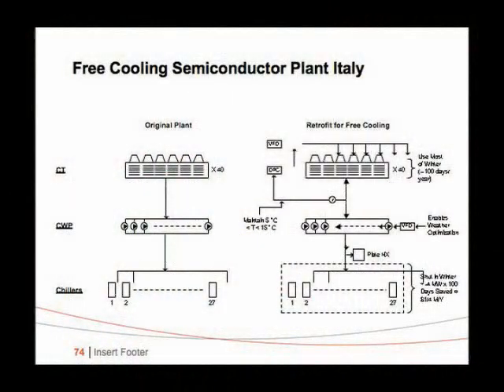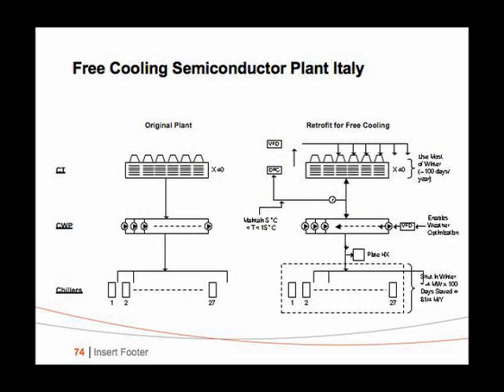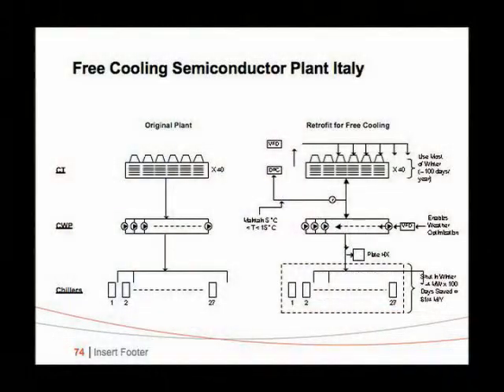But there's also good news. Italy. Some people used to run all the plants in winter. So we say, hey, it's a simple way. Get heat exchangers, use inverters, set up your controls. You can get free cooling. This is kind of a no-brainer. And free cooling for more than 100 days a year is 4 megawatts of saving.